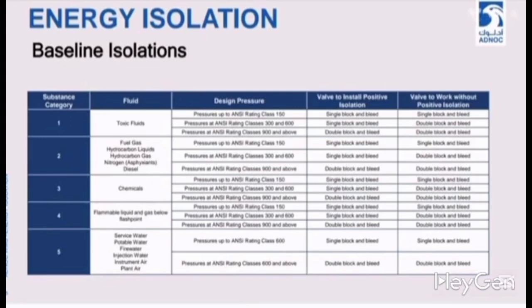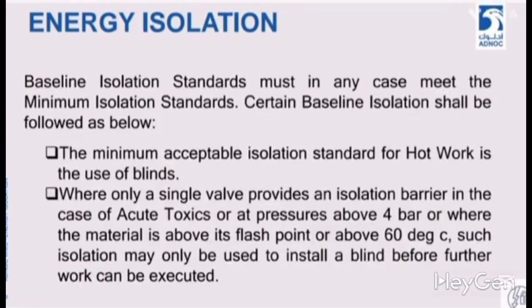Similarly, for fuels, gases, oils and chemicals, the baseline recommendation will depend on the pressure. The higher the pressure, the more will be required. We will have to ensure double isolation or positive isolation. We will discuss the baseline isolation in more detail in the next videos. What is the baseline isolation standard?